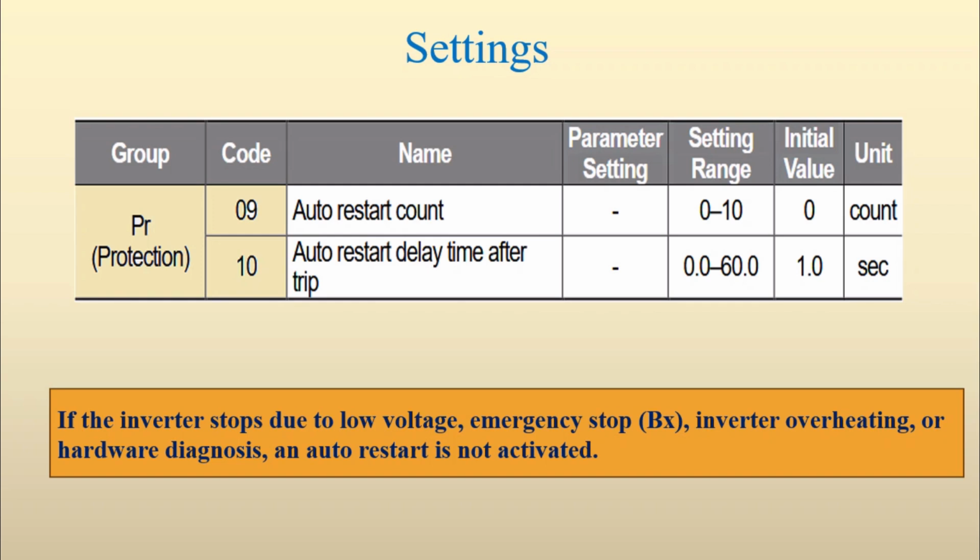But one thing you should keep in mind is that if these faults include low voltage, emergency stop, inverter overheating, or a hardware problem in the inverter, the auto restart feature will no longer function and won't be activated.